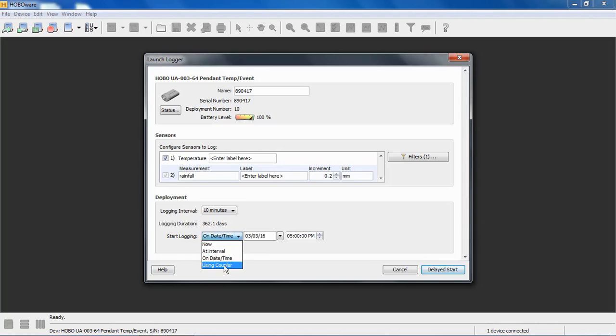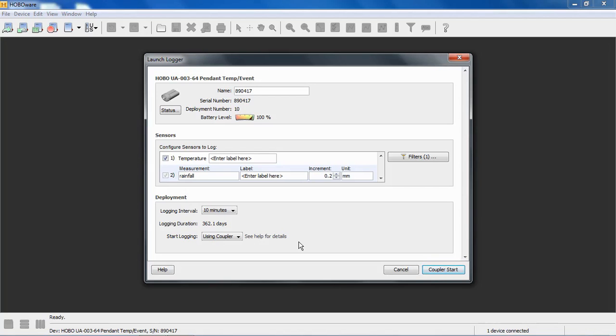This logger also supports a trigger start. We call it coupler start here. The way that works, that coupler that you have it plugged into in the base station or the shuttle, the black thing with the arm on it, there's a magnet in there. And so what you would do is if you select coupler start, you remove the logger from this coupler. Once the coupler start is completed, remove it from the coupler, take the coupler off your base station or shuttle, take the coupler out in the field with you with your data loggers. And when you're ready to do a coupler start, slide the coupler only onto the logger, leave it there for three seconds, pull it off, and the magnet on the coupler will close the little switch inside that logger and cause the logger to begin logging.